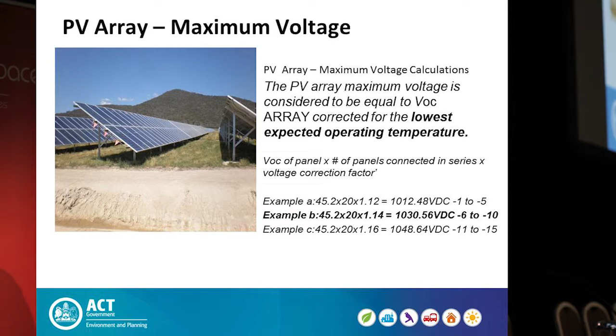I said earlier that temperature matters. In the ACT at this site, -6 to -10 is the actual temperature coefficient you have to use. You'll see in those calculations just how much the voltage changes when you put those numbers into the formula. What they've done, and this is common across the 3 solar farms we're building, is the calculations that have been done usually are in the -1 to -5 range. As you can see from that example, it's the difference between 112 volts maximum and 130.